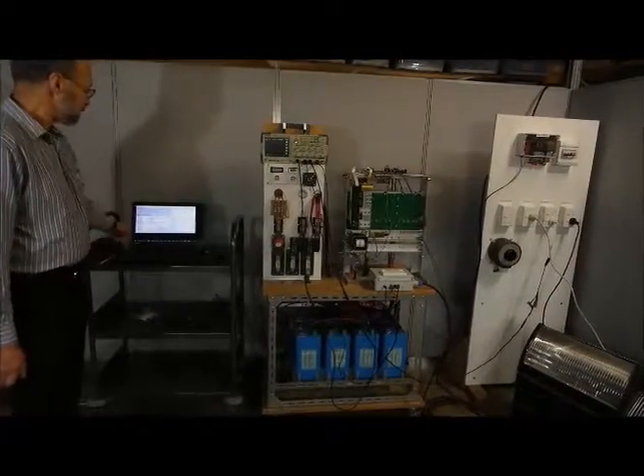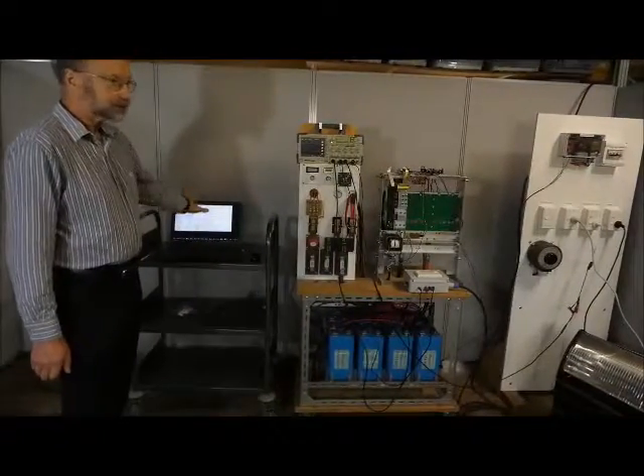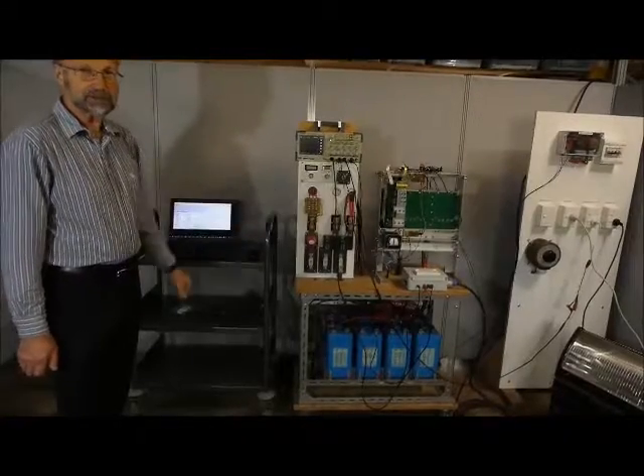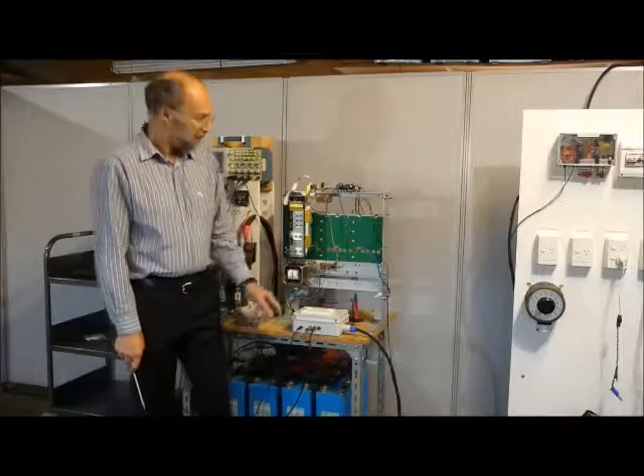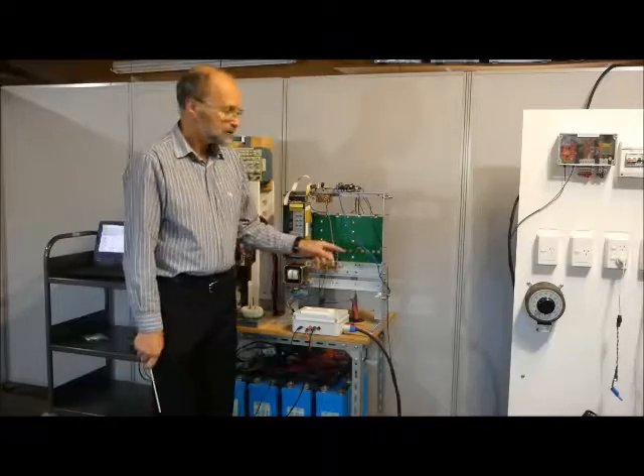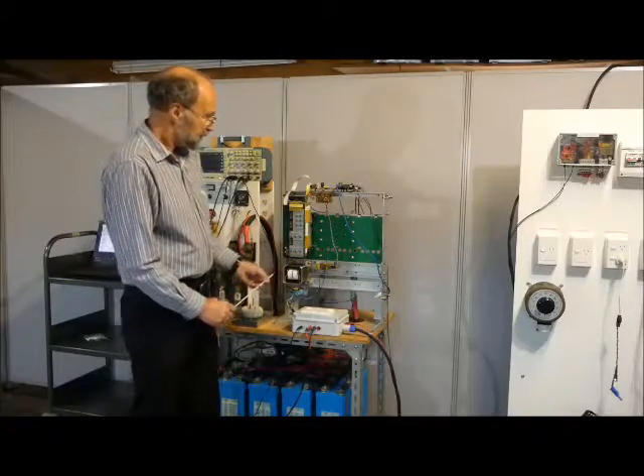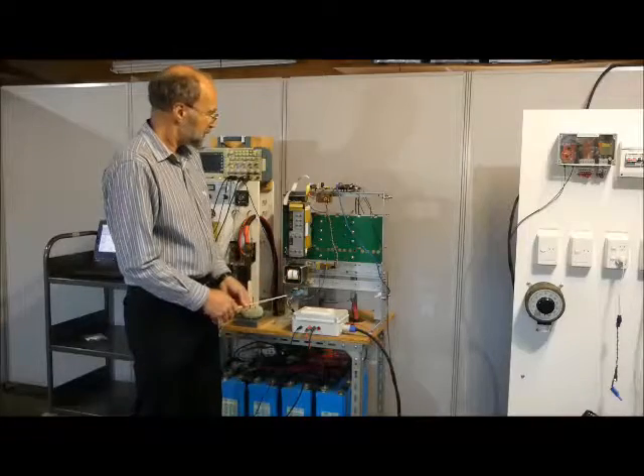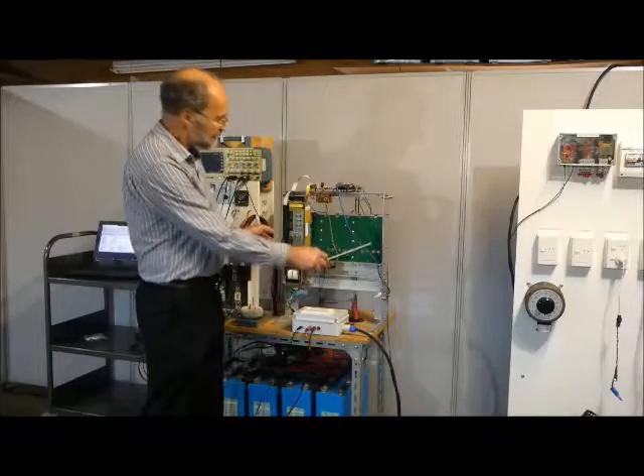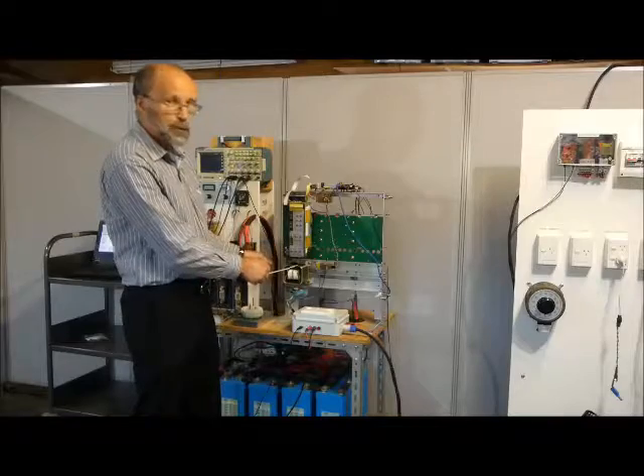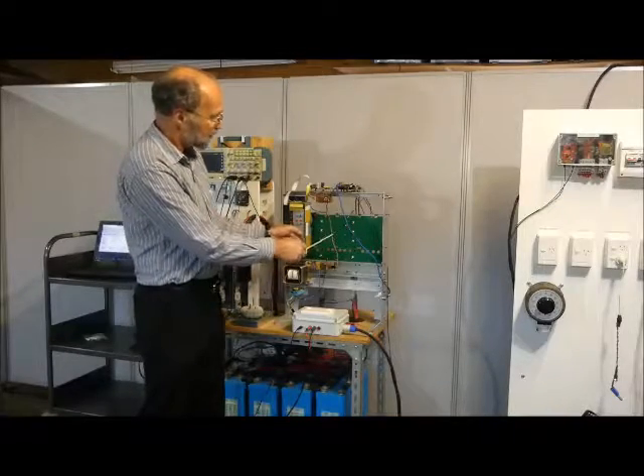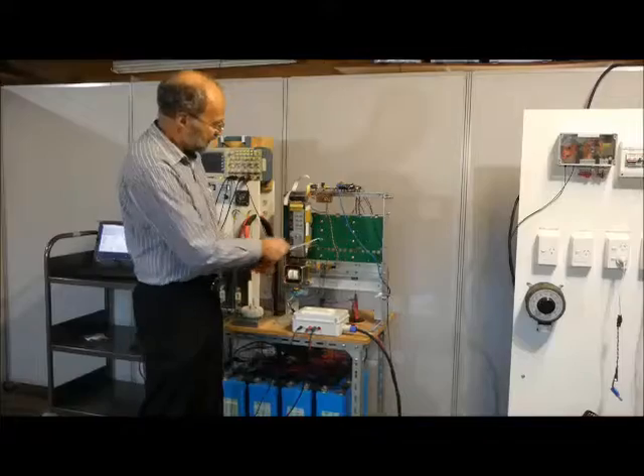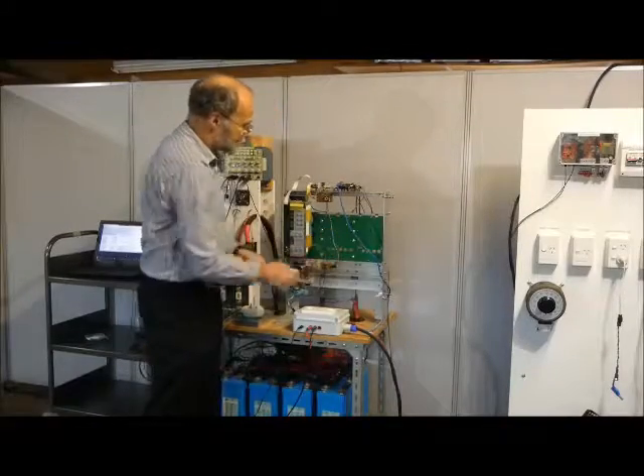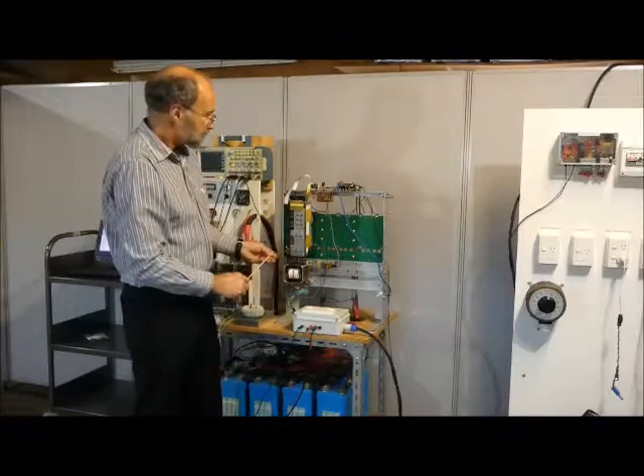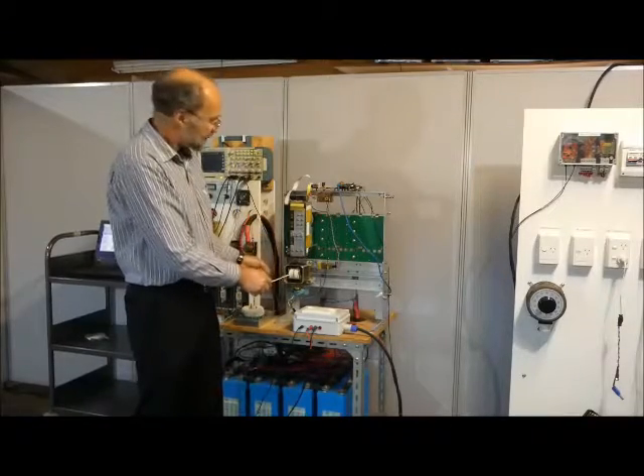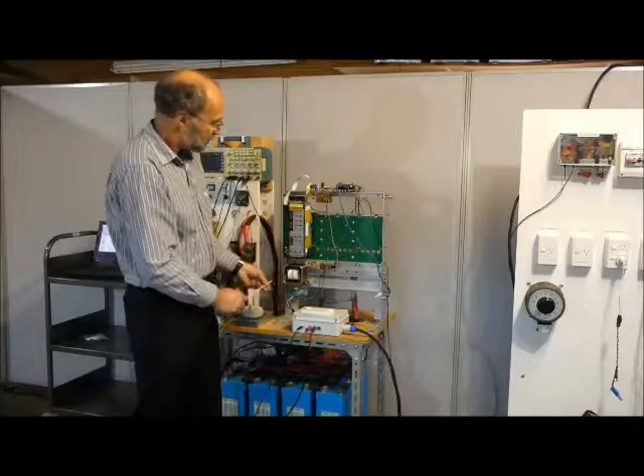Over here we have a laptop which allows us to control and monitor everything that goes on in the system. This is the inverter. This particular prototype was built for a marine application, so it's a 24 volt inverter, and it was built for a 20 kilowatt system. So we have 4 of these 5 kilowatt modules that can be mounted side by side on this capacitor board here. For the grid tie application, we're only using one 5 kilowatt module.